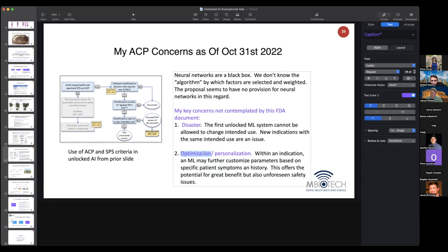If we're going to have changes in intended use, let's talk about optimization and segmentation — not about allowing a neural network to expand its intended use. Instead, let's allow it to have the opportunity to specialize and segment the patient population. This will still carry some safety risks, and that has to be subject to hazard analysis, but it's a much better starting point than allowing an unlocked system to expand its intended use.